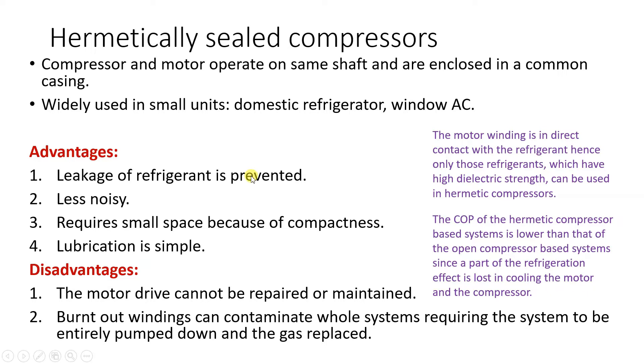Disadvantage: the motor drive cannot be repaired or maintained. Once the compressor is damaged or not working, you don't open the shell, check the problem, and weld it again. Once the motor drive or compressor is damaged, the whole compressor is discarded. Usually, what companies like Emerson do is: if it is inside the warranty period, they take back the compressor, bring it to their plant, cut the shell, check the problem, improve the design, and send you a new compressor.